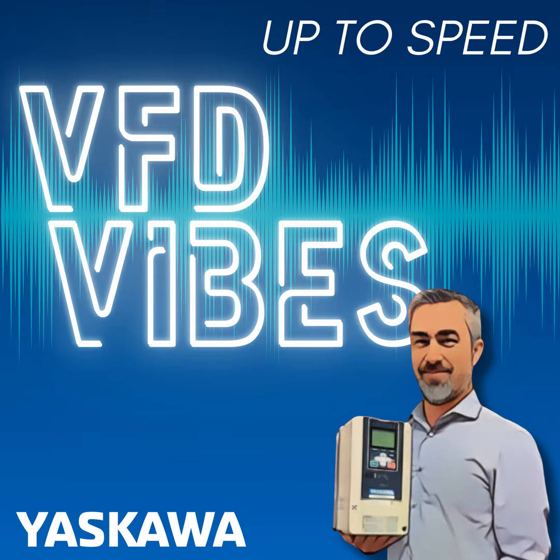So that aspect of grounding we refer to as equipment grounding or protective grounding, and bonding is all part of that. What is bonding? Well, bonding is tying wires to the dead metal parts of any piece of equipment. Dead metal parts are things that are not intended to conduct electricity, like cabinet doors, the walls, the back panels of cabinets, the cases of motors, things like this. These are all parts that are not supposed to have any electrical potential. These all have to get tied together and eventually tied to the surface of the earth, or grounded.